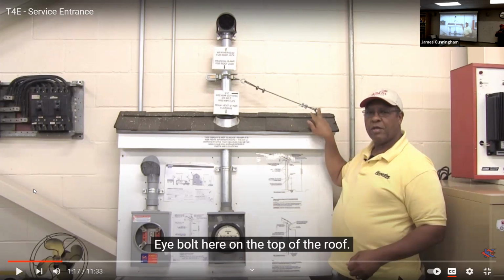So now the double top plate and my roof are supporting the mast from falling over in case of an earthquake. You have extra support, and so if we're retrofitting or putting in a service upgrade, even if the old panel was here with a mast on the outside, we have to open up the wall and put the mast inside the wall through the double plate and through the roof. So it gets that double surface so that it doesn't fall over in case of an earthquake. Or high winds. High winds can blow your wires back and forth, so that might pull your mast over also. So this acts for both earthquakes and high winds to really support that mast so that it doesn't fall over.